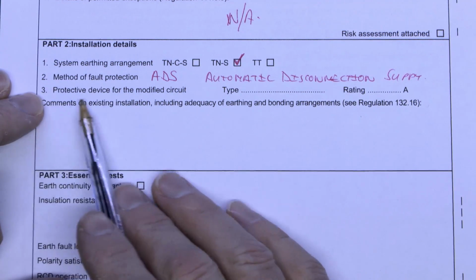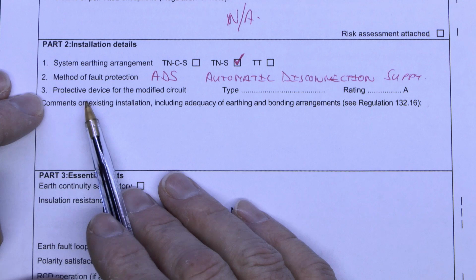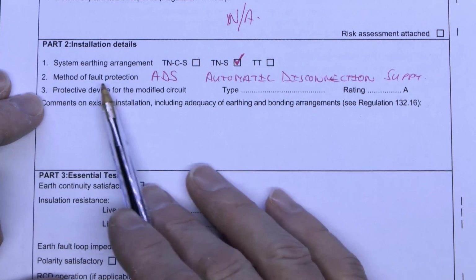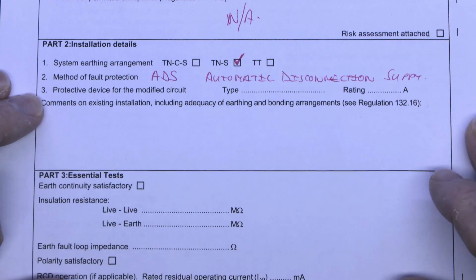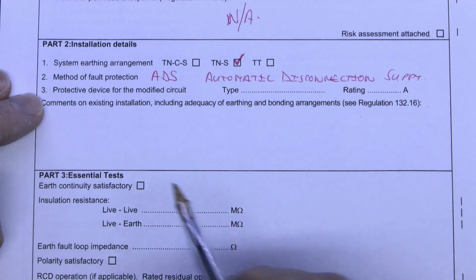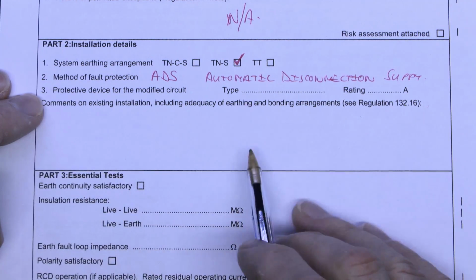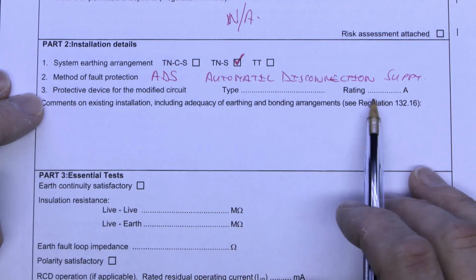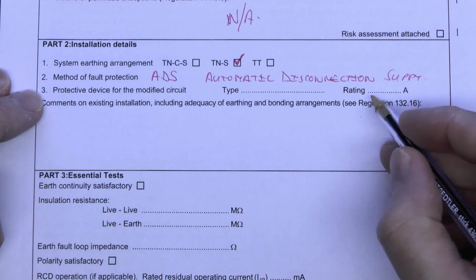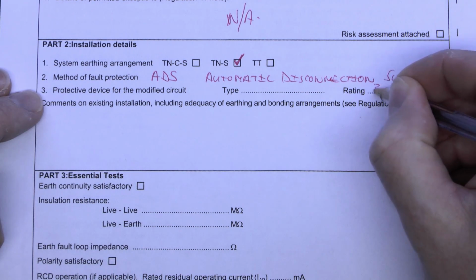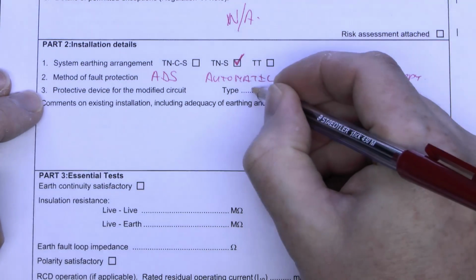Now, protective device for the modified circuit. So protective device means, say, the fuse or circuit breaker or whatever else. I think it pretty much ties in with the previous item. That's the method you're using, and then you're just going to give the information of what that thing actually is. So you've got protective device for the modified circuit, type, and also a rating. Now, obviously this depends on what you've actually got. So in this case, we'll say it was a ring circuit. We just added an extra socket to that.